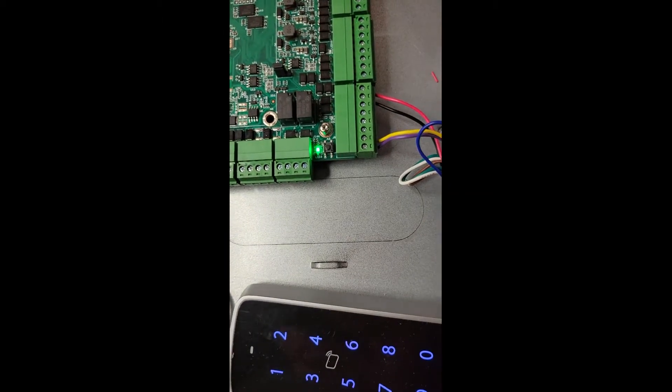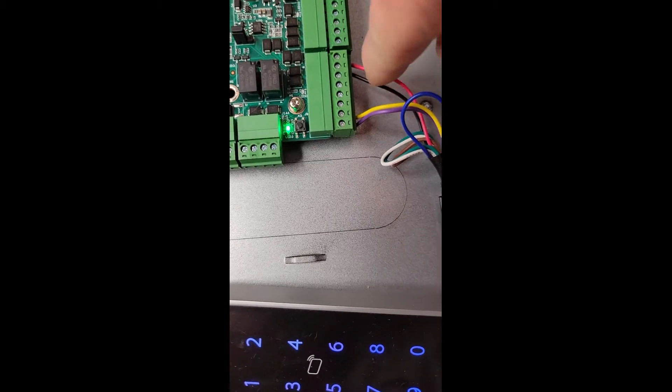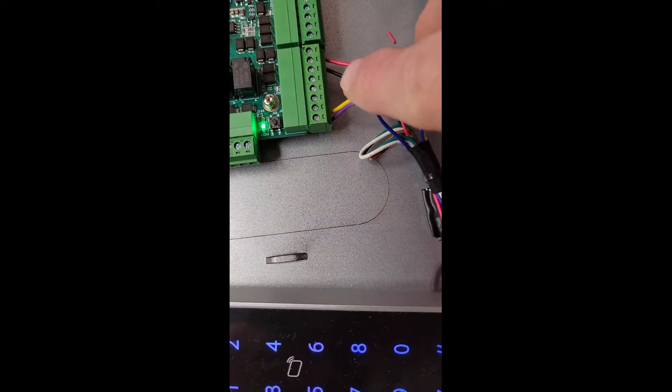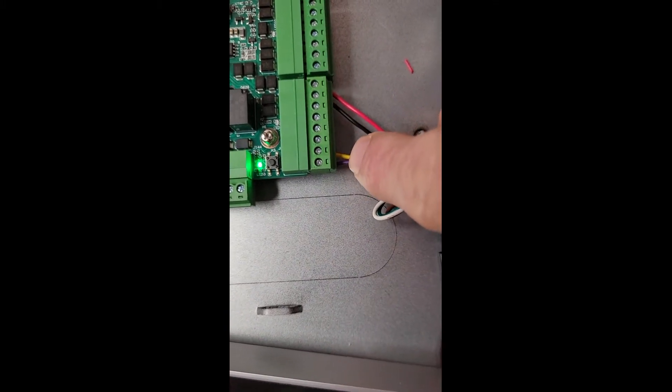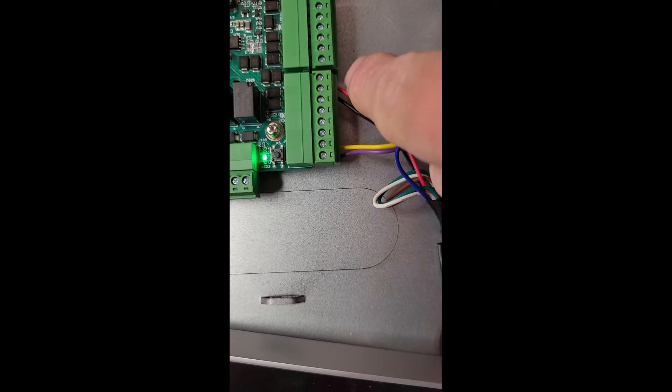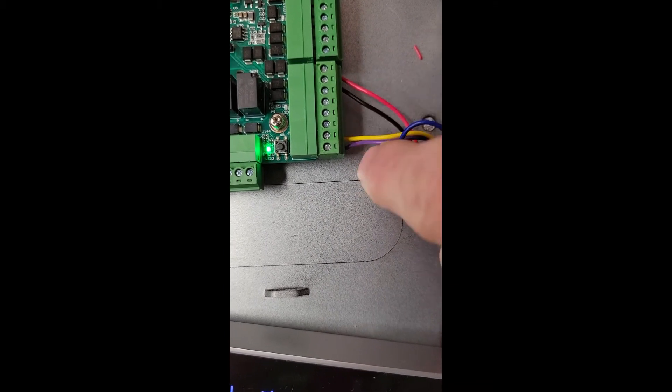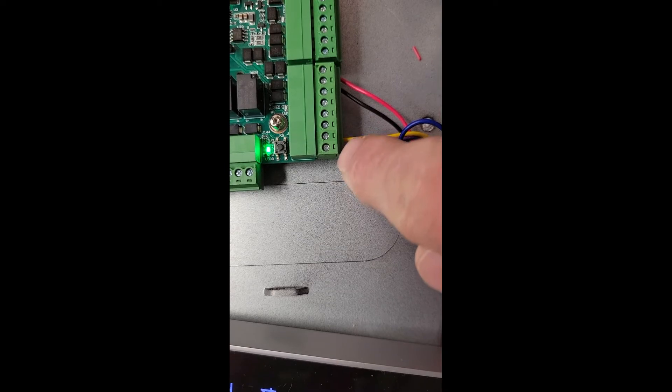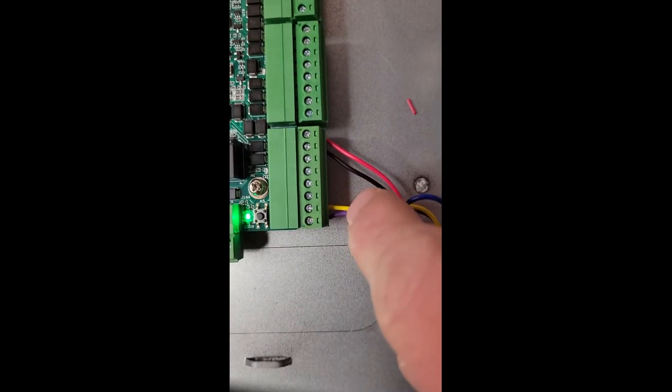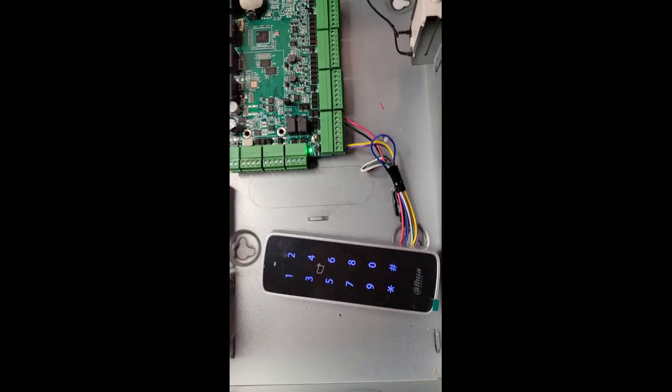So here on the terminal block we can see that our red and black wires are for power, and our yellow and purple are for the RS-485 connection. Red on the first terminal, black on the second, and then from the bottom, purple on the last, and the yellow goes to the second to last. That's our card reader.